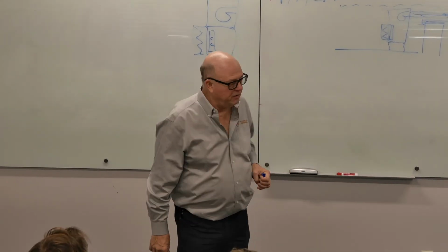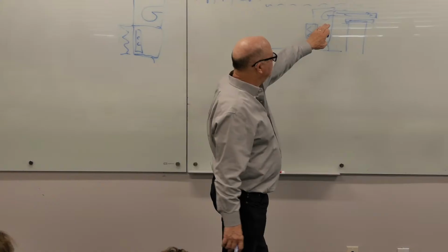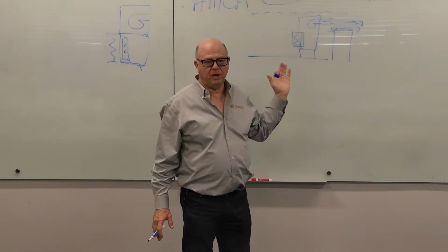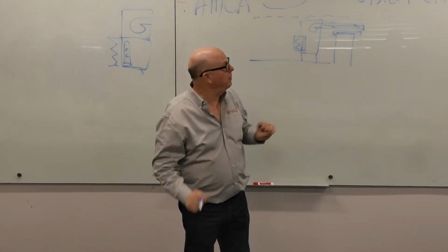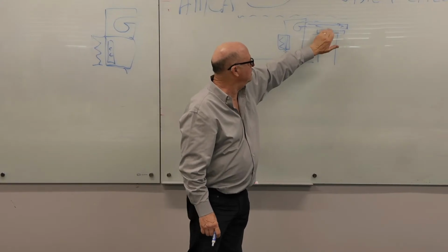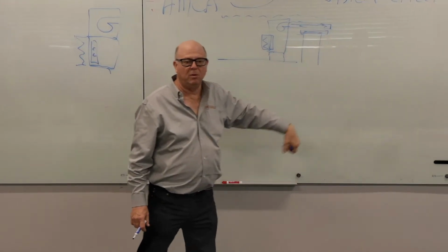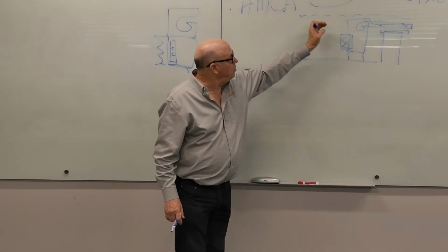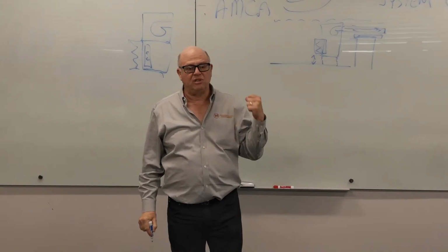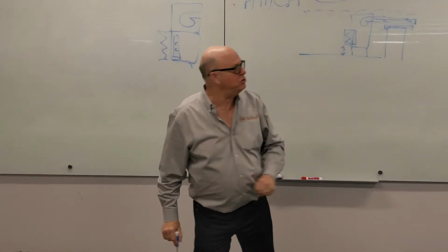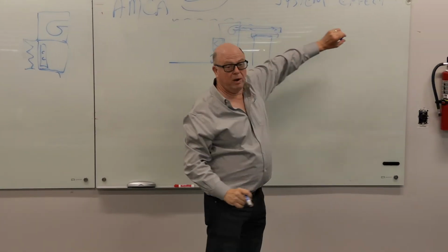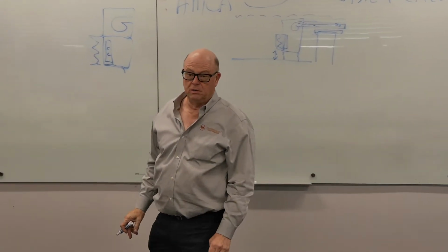He did a couple of different things. I don't know where he was on that subject at the end of his career, or how many feet he was doing. But you'd have lined duct, and if you were concerned about it, some additional stuff, you'd have the double wall gypsum, and you would have put it on a stand, and the height of this stand was the last thing that was determined based on the equipment submittal for the air handling unit and where you could get this thing to be right where you wanted it to be going over the tunnel.